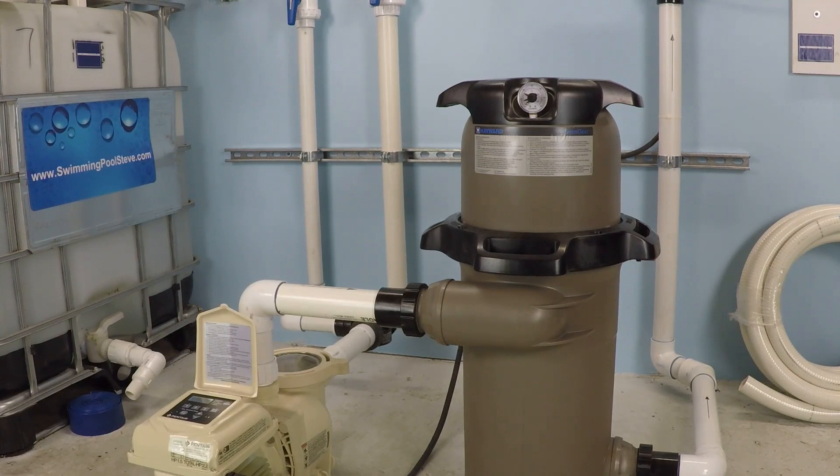Today we're going to be testing a Pentair SuperFlo variable speed pump — a 1.5 horsepower pump installed on a 2-inch plumbing system with a 150 square foot cartridge filter. We're going to run this pump at full speed, 3450 RPM, and take a look at both the flow rate and the electrical consumption. The question we're asking is: if we turn down the RPM by 500, what difference will that make to the flow rate and electrical consumption? Let's get started.